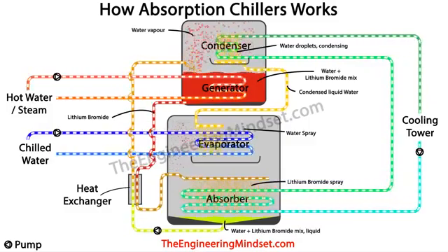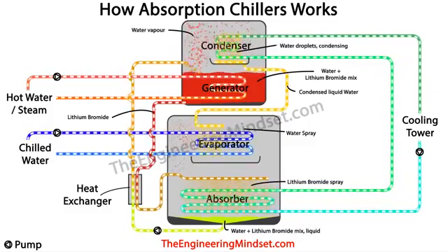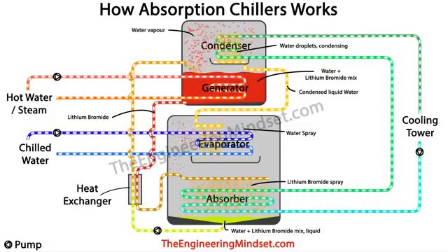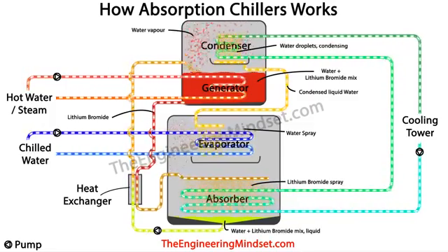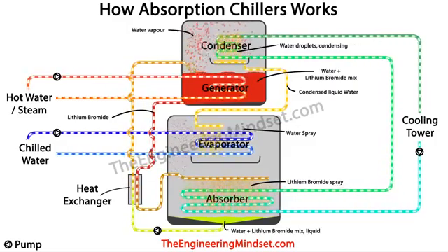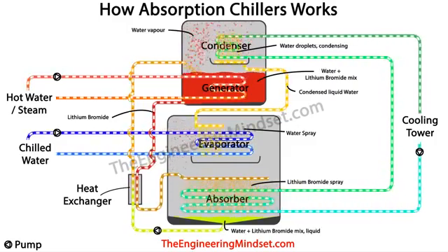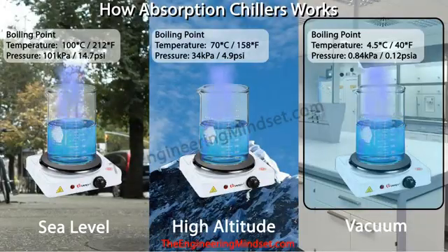Remember, the two waters never mix. They're always kept separate and they are separated by the pipe wall. As this heat transfers into the water on the outside of the tubes, this outer water will evaporate into a steam or water vapor due to the low pressure of the chamber. As it evaporates, it carries away all the unwanted heat with it. And remember earlier we did learn how water boils at lower temperatures under low pressure.